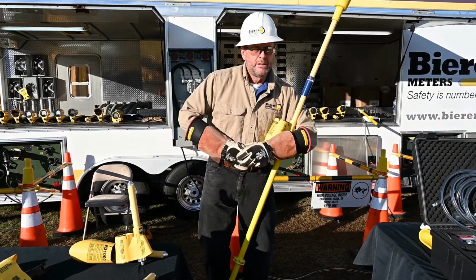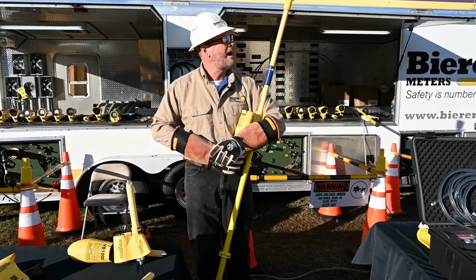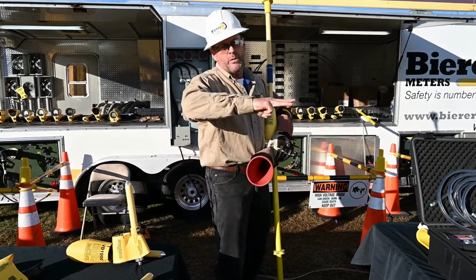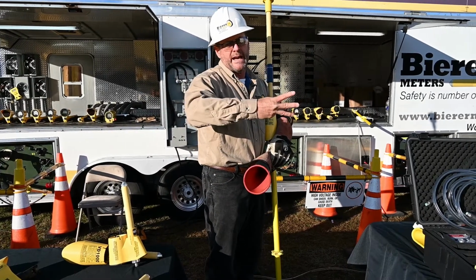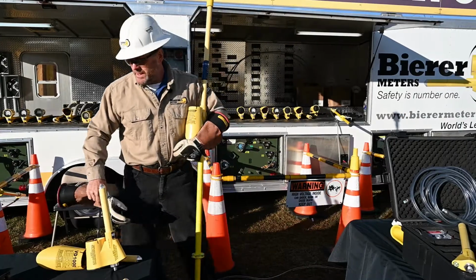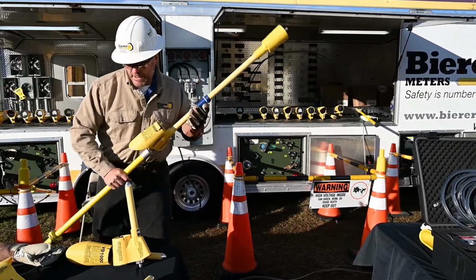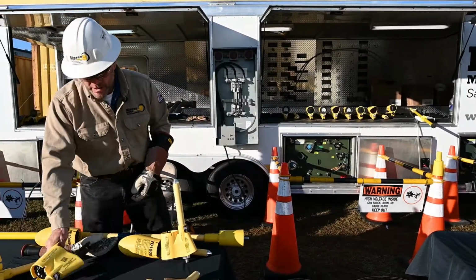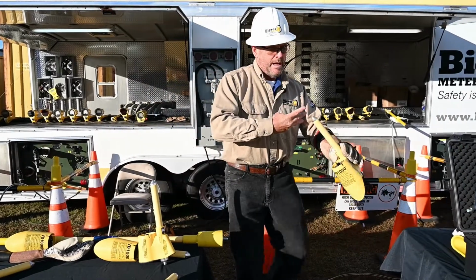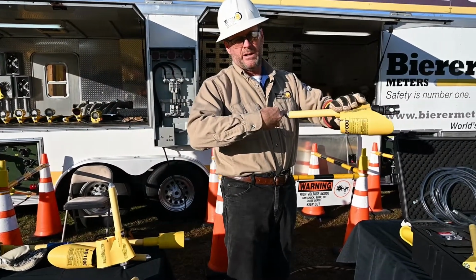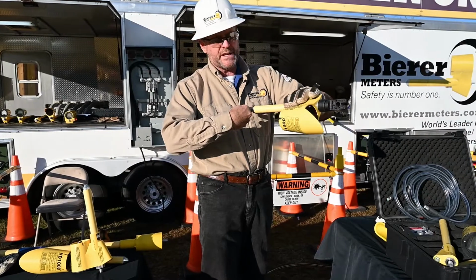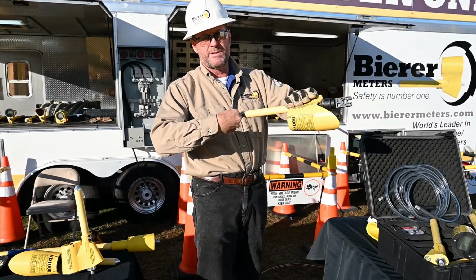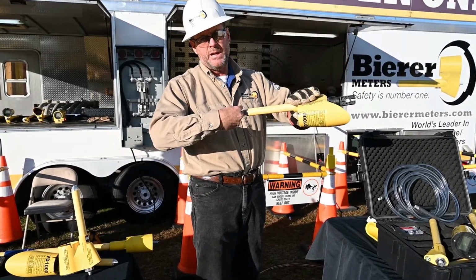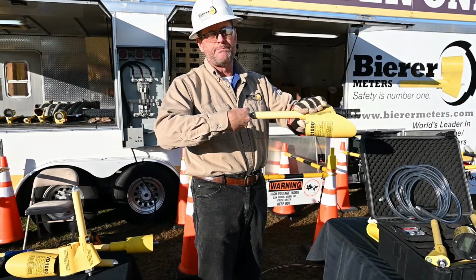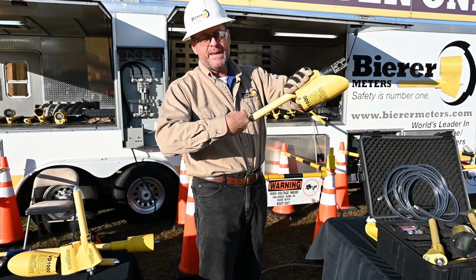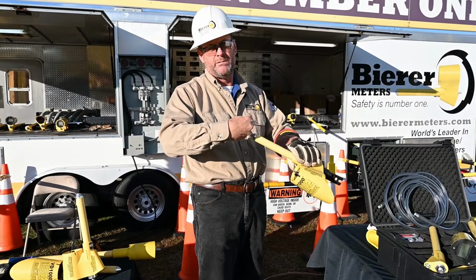On an underbuild, or with close wires to each other, whether it's a horizontal stack or a vertical stack, you want to come to that potential with your tool, and you want that tool perpendicular, at a 90-degree angle with the conductor you're touching, let's say the long source here, with the conductor you're touching, and as much as possible a 90-degree angle from the other conductors above and below.